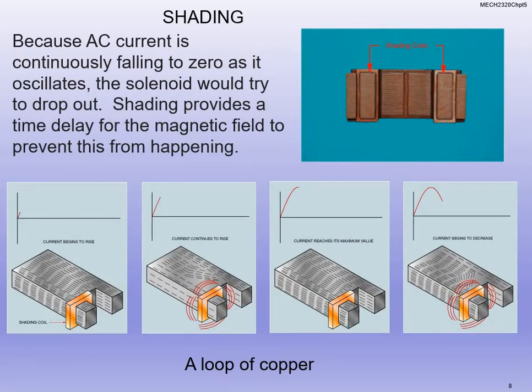We use shading coils in the AC piece. AC is constantly changing signals — plus, minus, plus, minus — and we don't want the solenoid to fall out. When current is on positive, the solenoid creates the magnetic field; it goes negative and changes the other way. We use shading so that with AC it still remains constantly on. As current begins to rise, the shading coil creates that magnetic field. When the current reaches its maximum, it continues to kick on the field. We change the field in the other direction — changing the polarity — so that the contactor can stay closed as AC changes polarity.